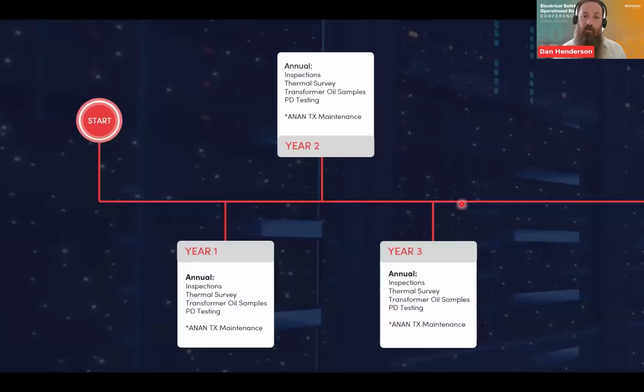So based upon those bits that we've talked about from 70B, which we're focusing on our theoretical network that we've got. Essentially, we've done our condition assessment at the start. Eddie's just come into his role. He's built his asset list, done his condition assessment, and in theory, we'll cover these a bit more in depth as we go. But in theory, the annual stuff that they're going to do is inspections on an annual basis. We'll talk through frequencies and what's recommended and best practice. But essentially, we're going to be doing inspections of our switch rooms, our substations, our switchgear, our transformers, so everything within there, batteries. We've seen in there that it recommends a 12-monthly thermal survey, so thermography.